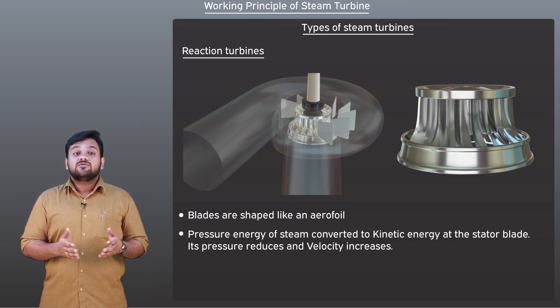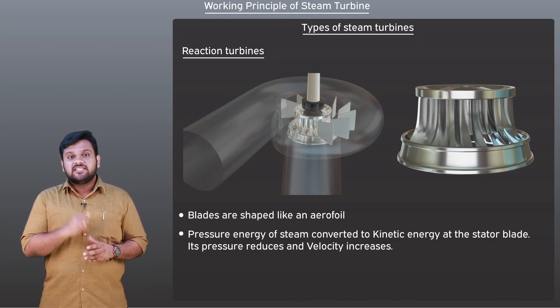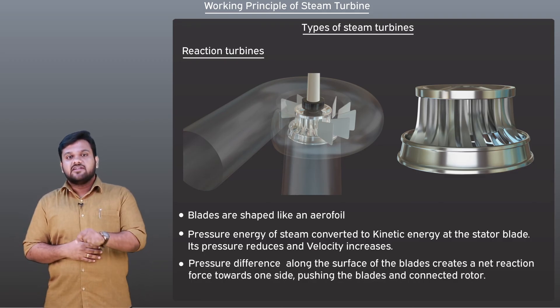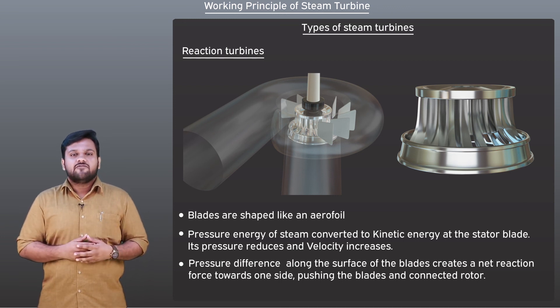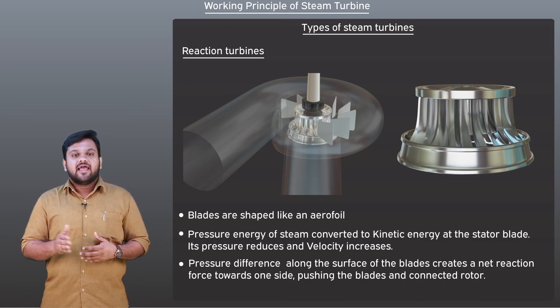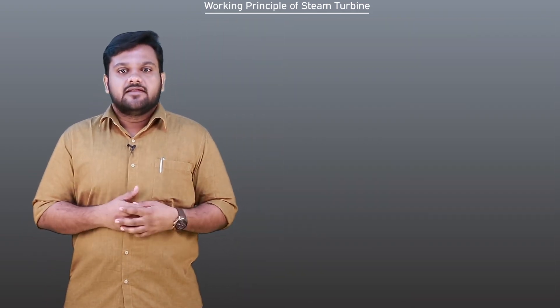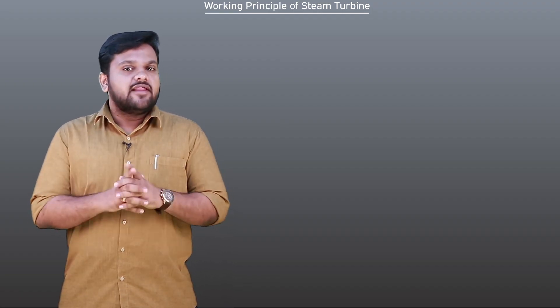When the steam flows along the moving blades, because of the aerofoil shape, it loses both velocity and pressure, and a pressure difference is created along the surface of the blade. This pressure difference creates a net reaction force towards one side, pushing the blade and hence the connected rotor. Both types of turbines are finally connected to a generator via a gearbox fixed on the central rotor, and the generator produces the required amount of electricity.